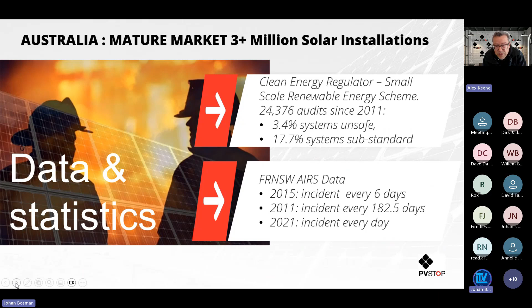That will start as an electrical fault but could escalate to a significant fire event. Fire and Rescue New South Wales incident response data—let me correct myself—in 2011 they were having an incident involving PV systems every 182 days. By 2015 that had increased to every 6 days. By 2021, incidents were occurring every day involving PV systems. That's now climbed to around 3 to 4 incidents per day across Australia. To be honest, these are incidents not just where the PV system is at fault, but where it also becomes involved indirectly and impacts first responder operations.